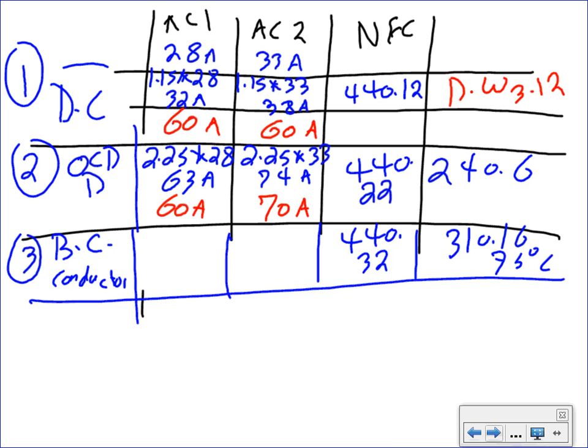Okay, it says 1.25 times the nameplate current, 1.25 times 33. Okay, what's the first amps? I can't hear it. 35 amps. Second one? 41 amps. Okay, now these are meaningless unless we convert them into dollars, which is AWGs.